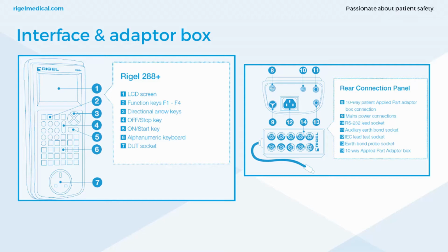9 is our main power connection for the safety analyzer. And we've got our 10-way applied part adapter box connection, RS232 lead socket for data transfer, firmware updates, etc. We do have Bluetooth in this device, but if you prefer a cable connection, it does have that option. And then 11, which is your auxiliary earth bond socket, and 13, which is your earth bond probe socket. And this is where you'll be doing your point-to-point testing as well. And also if you need an alternative earth path, so auxiliary earth bond socket is used for that as well. So with this you can do point-to-point earth bond and point-to-point enclosure leakage tests with the Rigel 288 Plus.